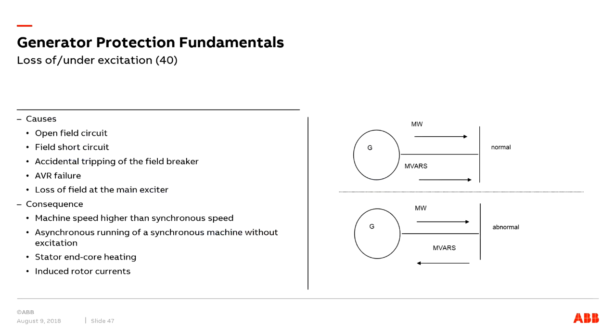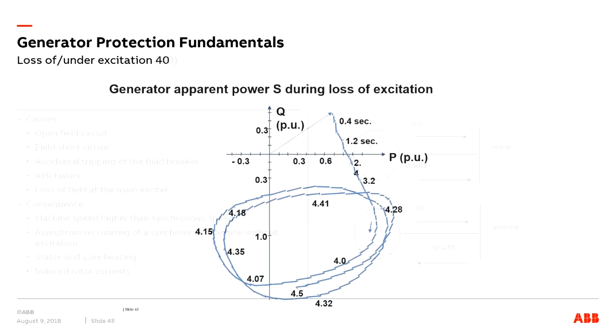Okay, so loss of excitation could be due to an open field circuit or a field short circuit, accidental tripping, or loss of field at the main exciter. The consequence of such a situation is that the machine speed can go higher than the synchronous speed. It can cause asynchronous running and stator end-core heating, and it can also induce rotor currents. Okay, so that needs to be protected as well.